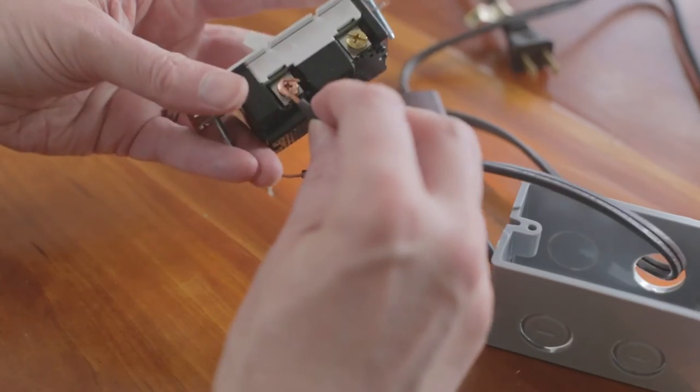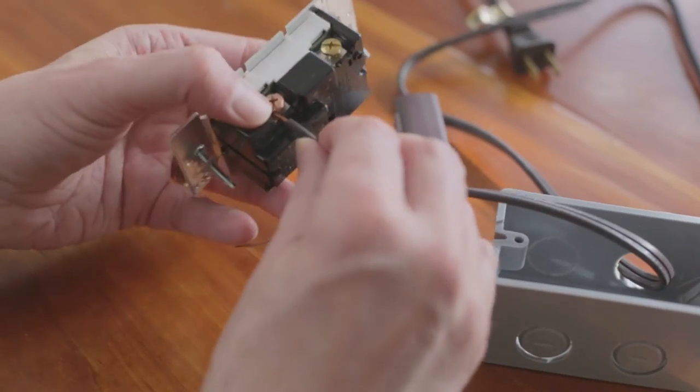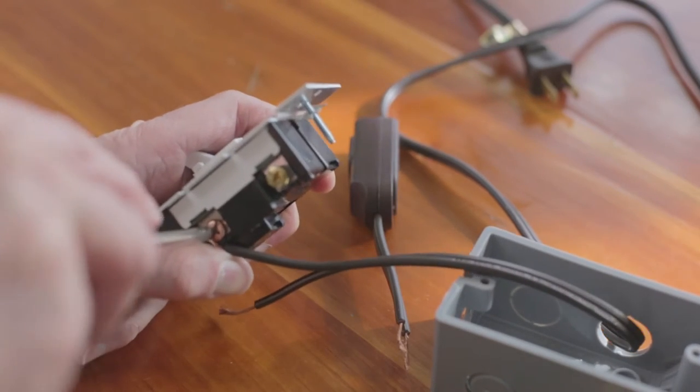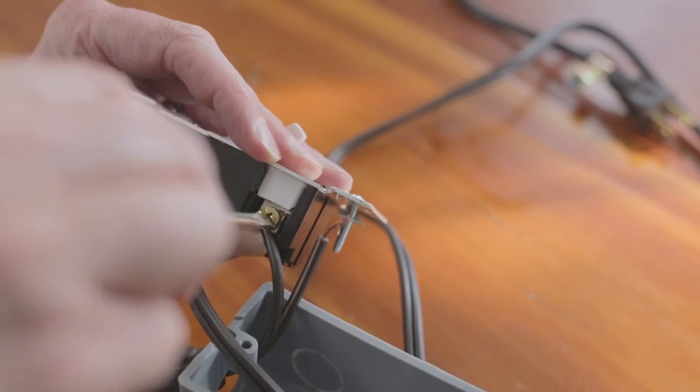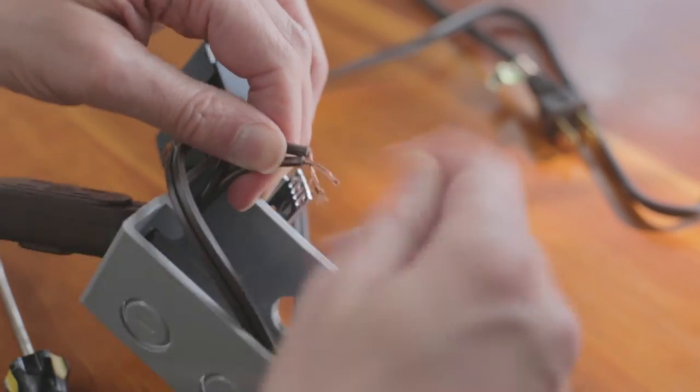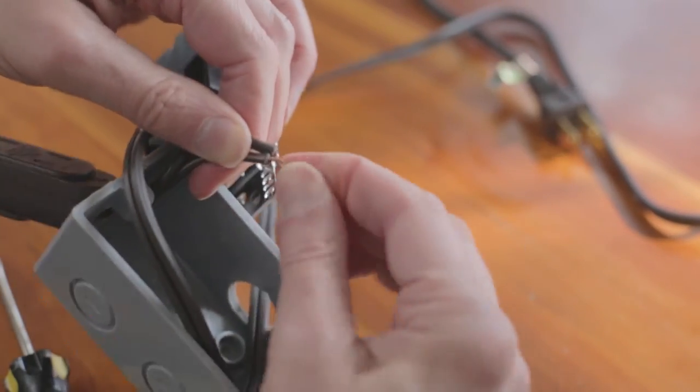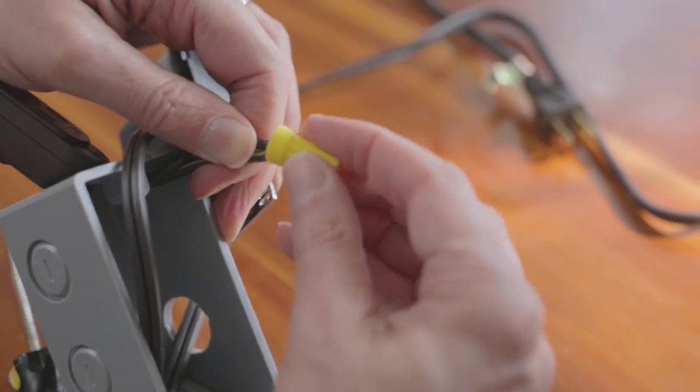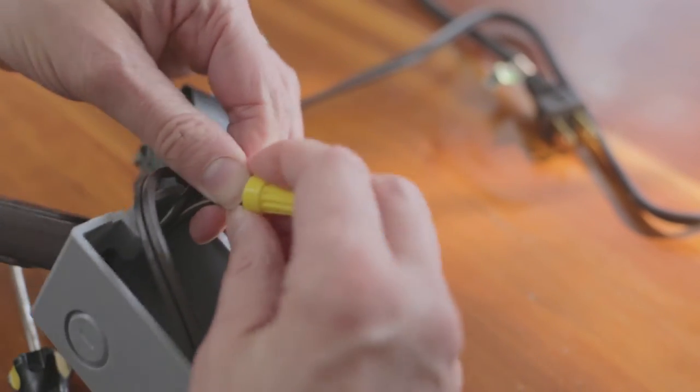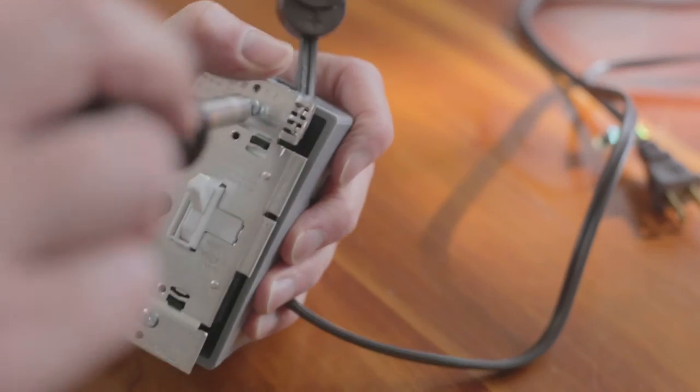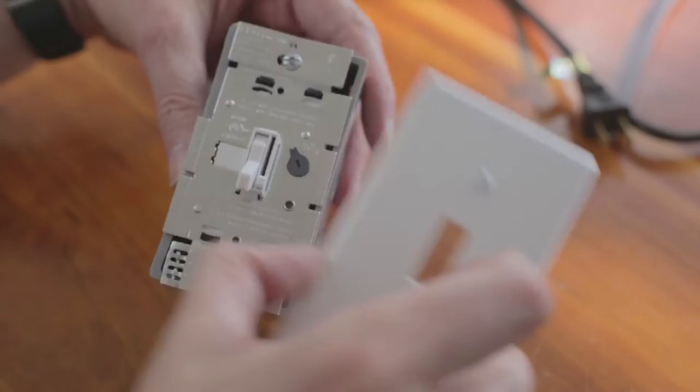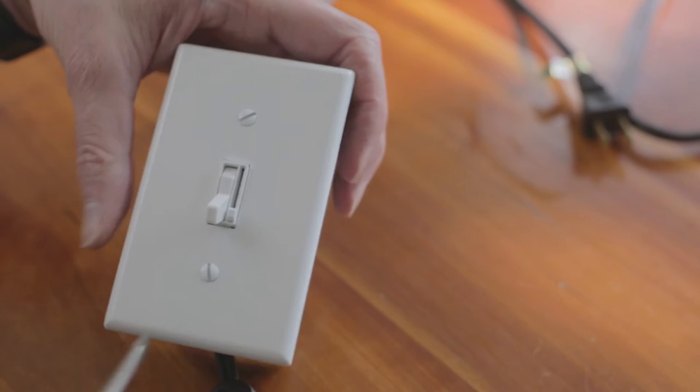Then I wire the incoming hot wire to the brass screw on the dimmer, out on the silver side. Since we're wiring the dimmer into the hotline, the neutral will just be wired right through. Remember, we are not breaking neutral, but the hot. Then I wire the neutral back together with a wire nut. Then I'll screw the dimmer into the box with a cover plate, and we have a portable dimmer.